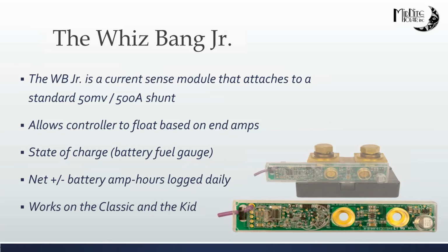Now, what that means in a nutshell is that if you buy a MidNite E panel, you buy an Outback sheet metal box for their equipment, or you buy a Magnum box for their equipment, they're all going to use that same shunt. And it has a specific bolt pattern that we match to. That makes it much easier to install. You're not crimping ring terminals on wires or trying to get wires into that shunt. It's just going to bolt right on as shown, and it allows us to monitor the current flow in and out of the battery.